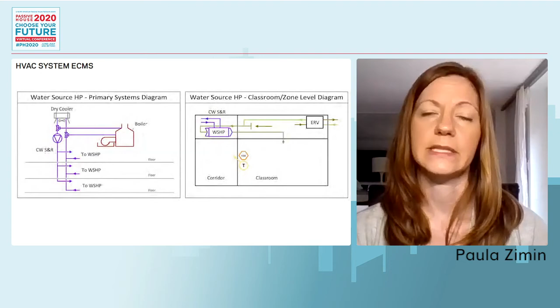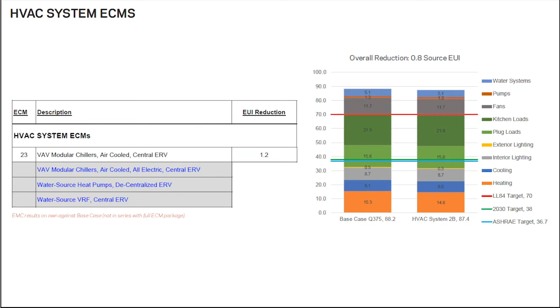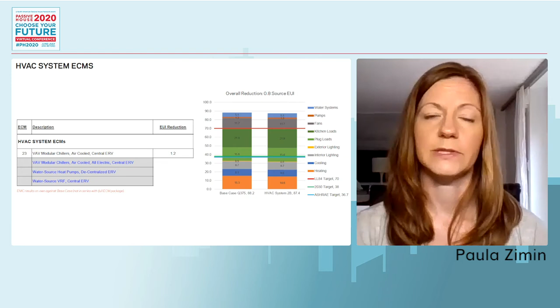We did investigate a couple of iterations of a VRF, a water source VRF, as well as an air source VRF. And at the end of the day, it seems like with all of the restrictions and with the optimization of the chillers and the boilers, the VAV modular chillers and boilers and central ERV on the rooftop units was really sort of the most energy efficient way to heat and cool and ventilate this building. So there wasn't too much of a change from the base case scenario to what is being recommended for this particular building. On the next slide, we'll talk about some of the other things that we investigated.